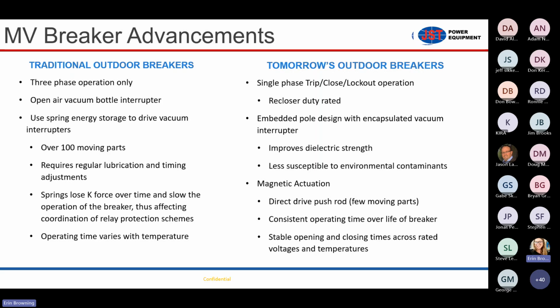So we have a substation device with circuit breaker duty in terms of continuous current rating and interruption rating, but it has the ability to do single phase trip, single phase close, so that we have the effects of and the benefits of reclosing on momentary and permanent faults. I'll get into more detail on that shortly. We've also seen improvements in the interruption device and the pole itself. So here we're talking about vacuum interrupters, and how that vacuum interrupter is installed and mounted.